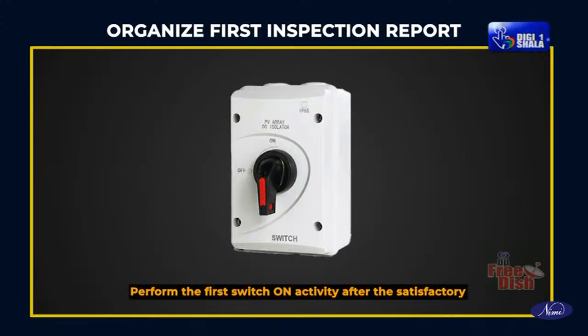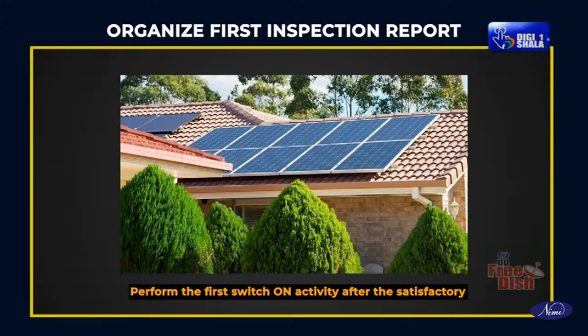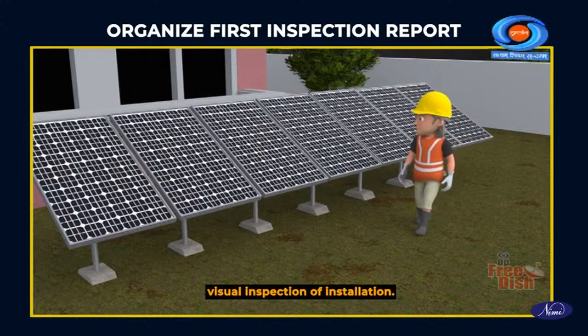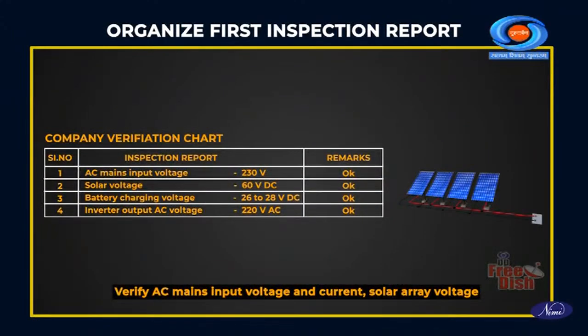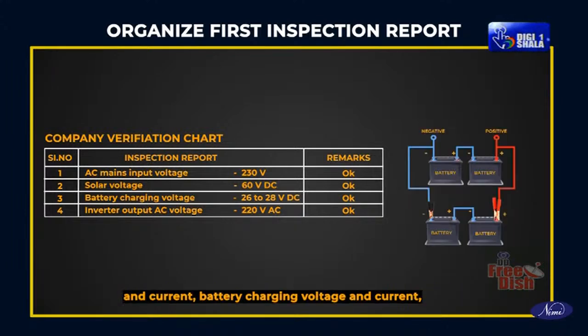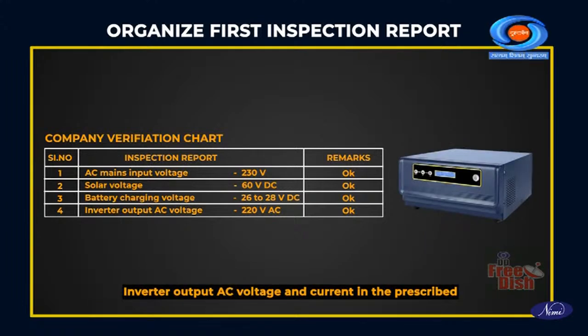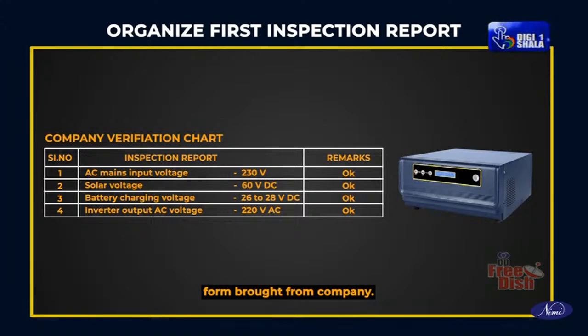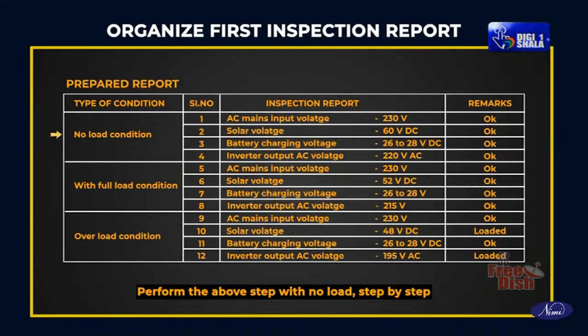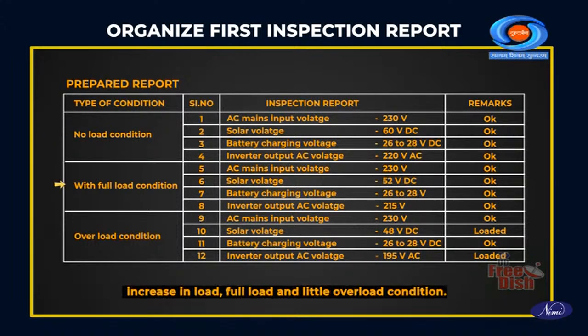Perform the first switch on activity after the satisfactory visual inspection of installation. Verify AC mains input voltage and current, solar array voltage and current, battery charging voltage and current, inverter output AC voltage and current in the prescribed form brought from company. Perform the above step with no load, step-by-step increase in load, full load and little overload condition.